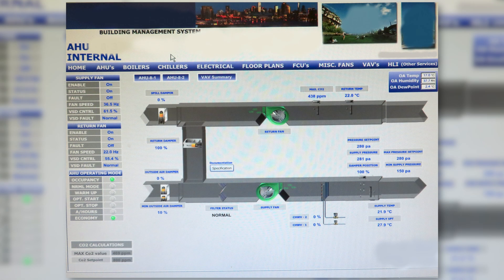In this third and final example, I think this is an old Schneider or TAC BMS - some of you older folks might recognize it. Again: supply fan at the bottom, return fan at the top, dampers on the left, supply temperature and pressure resets. This graphic is great for the construction phase to make sure the BMS is commissioned, and then presenting it to the customer. It's also good during maintenance to diagnose that things are basically working. But I think you'll agree that looking at these three graphics and three modern day air handling unit graphics, they're not that different - not a lot has changed other than the visual appearance.